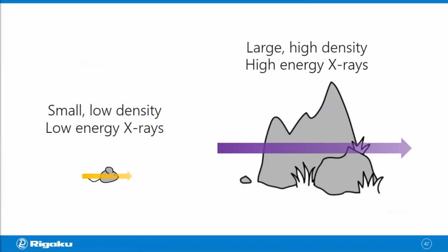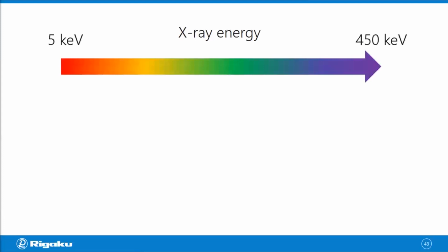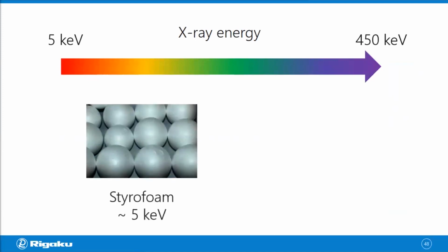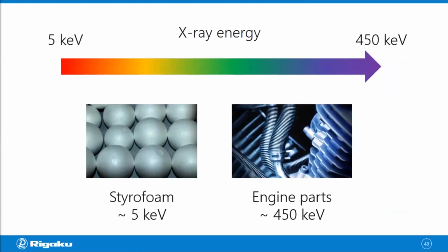Now for the range of X-rays you can use, for the commercially available X-ray sources, you can find different sources from 5 keV to about 450 keV. And that energy range translates into density. For example, styrofoam can be imaged with 5 keV X-rays. And if you want to look at something like engine parts made of stainless steel, then you want to go to 450 keV to see them. So that's, density wise, just roughly the range you can look at with those X-rays.